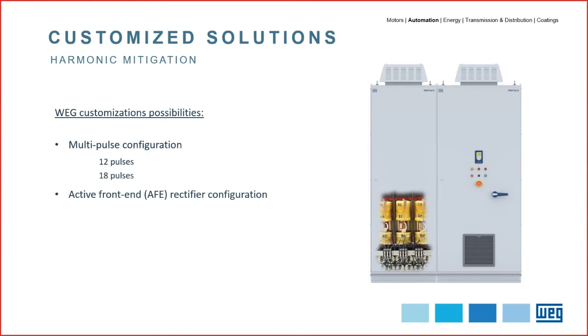Another option is the active front-end rectifier configuration, or a regenerative VSD panel. This option is mostly considered by the market for the benefit of power regeneration to the grid during fast braking and high inertial loads, or when several motors are connected by a single DC link. This is also an option for harmonic mitigation.